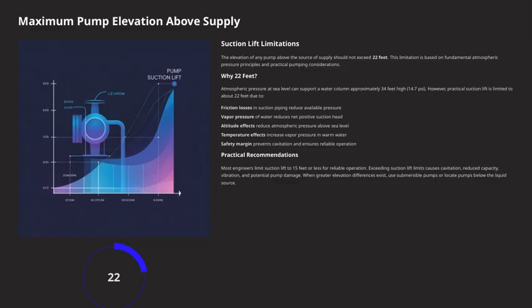That's why most engineers recommend keeping suction lifts to 15 feet or less for reliable operation. When higher elevations are unavoidable, it's better to consider using submersible pumps or positioning the pump below the liquid source to ensure smooth operation and avoid these issues.